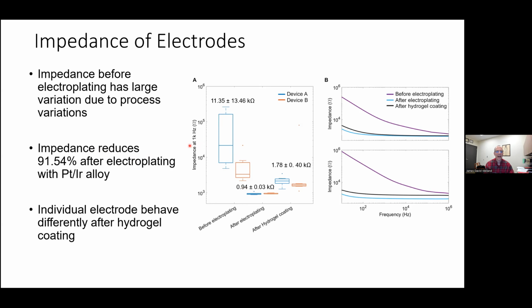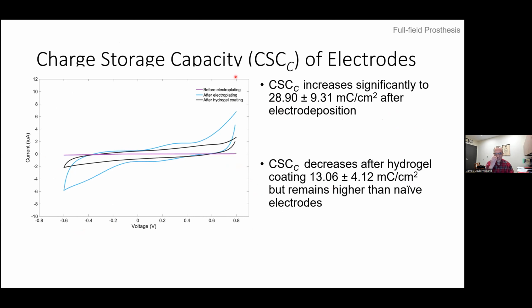What we see after electroplating, which is this data here, is that we've reduced not only the impedance overall, but we've reduced the variability. So electroplating had a cleaning effect. Adding a hydrogel layer on top of the electrodes, we were worried that would effectively insulate the electrodes, but hydrogel actually has a reasonable conductivity, so that only increased the impedance of the electrodes a small bit. This shows some impedance spectra in two individual cases. Charge storage capacity is an important factor for stimulating electrodes, and we've shown, without going into too much detail, that the purple line is before electroplating.